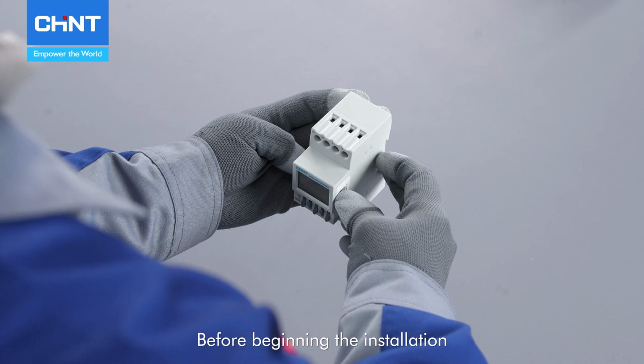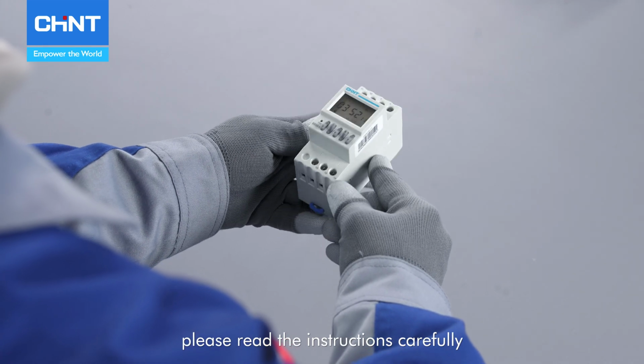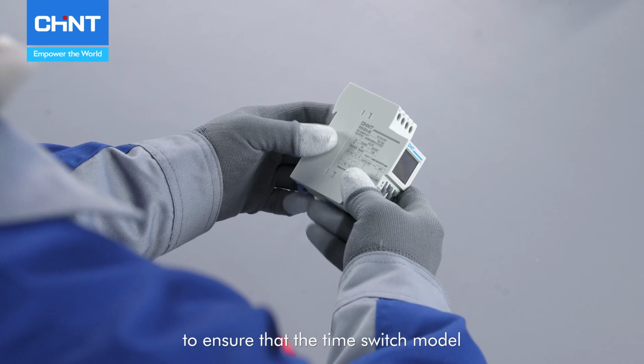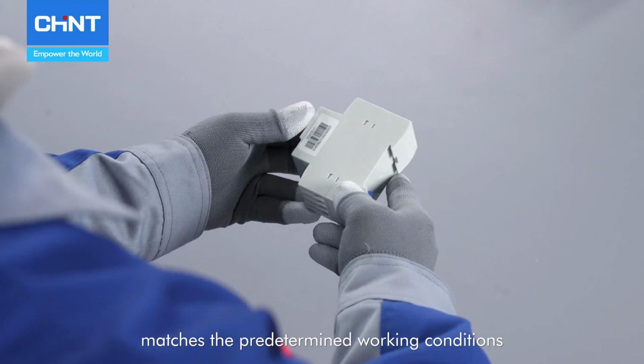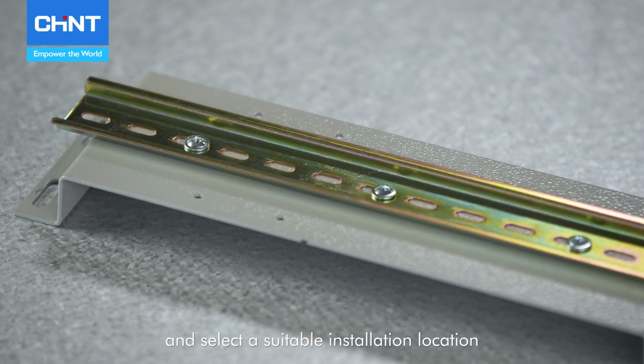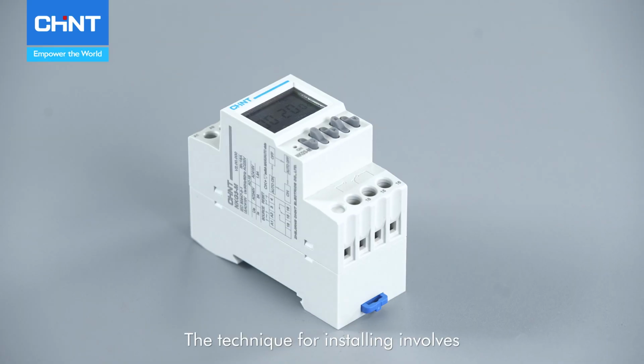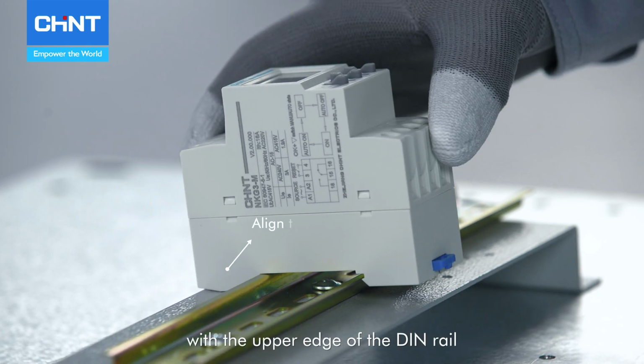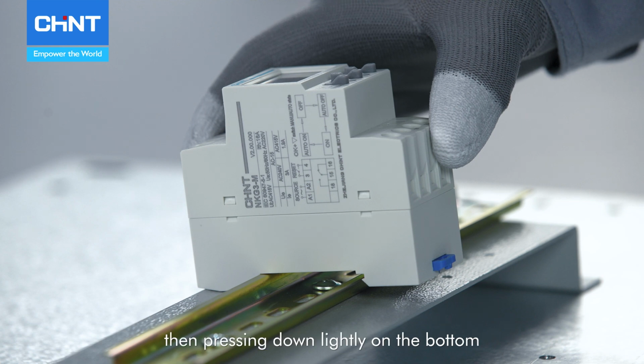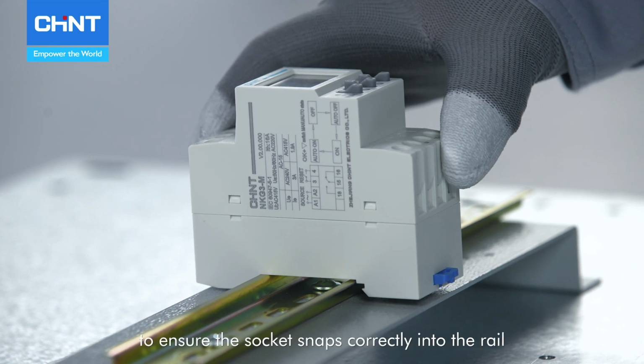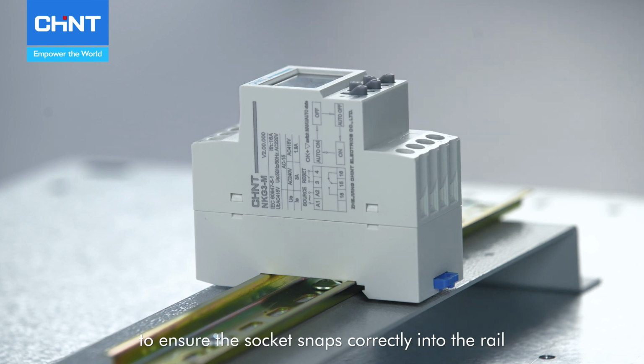Before beginning the installation, please read the instructions carefully to ensure that the time switch model matches the predetermined working conditions, and select a suitable installation location. The technique for installing involves first aligning the top end of the time switch with the upper edge of the DIN rail, then pressing down lightly on the bottom to ensure the socket snaps correctly into the rail.